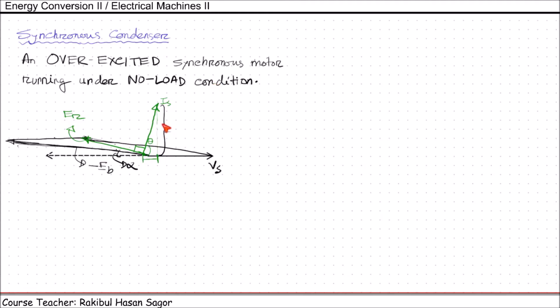We can see from here that the synchronous condenser has a leading power factor. This makes it useful for power factor correction of industrial loads. We know both transformers and induction motors draw lagging or magnetizing currents from the line. On light loads, the power drawn by induction motor has a large reactive component and the power factor has a low value. So if we connect a synchronous condenser in parallel with those loads, the synchronous condenser will supply some of the reactive power required by induction motors. Eventually this improves the overall power factor and reduces the reactive current required from the grid.